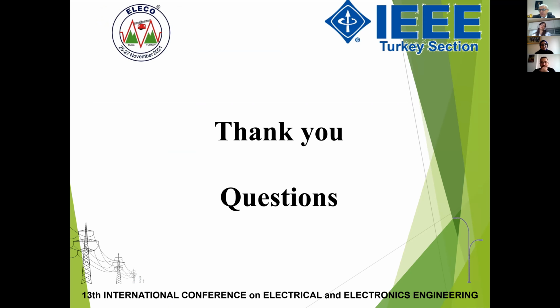Harmonics are a problem in electrical systems every time, in production, distribution, or consumption. In your study, do you think only the effects of voltage, or current harmonics too? No, we have added the harmonics on the primary voltage, and we saw that it affects the eddy current more as compared to the other losses.